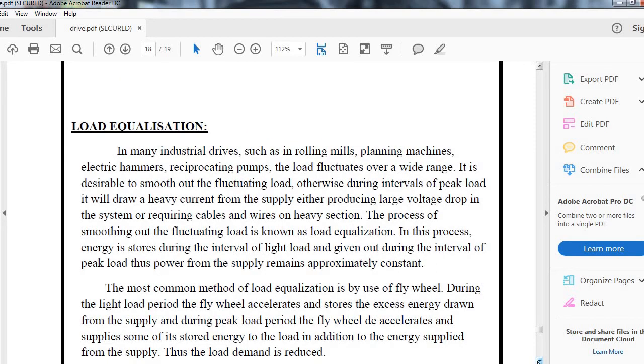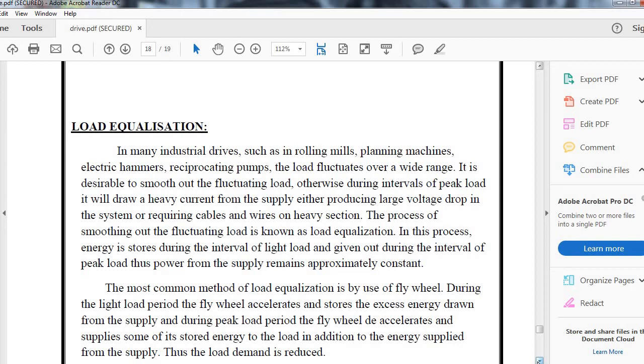Load equalization: in many industrial drives such as rolling mills, planning mills, machines, hammers, and reciprocating pumps, the load fluctuates over a wide range. It is desirable to have smooth fluctuations of load, otherwise during peak load intervals, it may draw heavy current from the supply, producing large voltage drop in the system or requiring cables with heavy sections. The process of smoothening out fluctuating loads is known as load equalization.